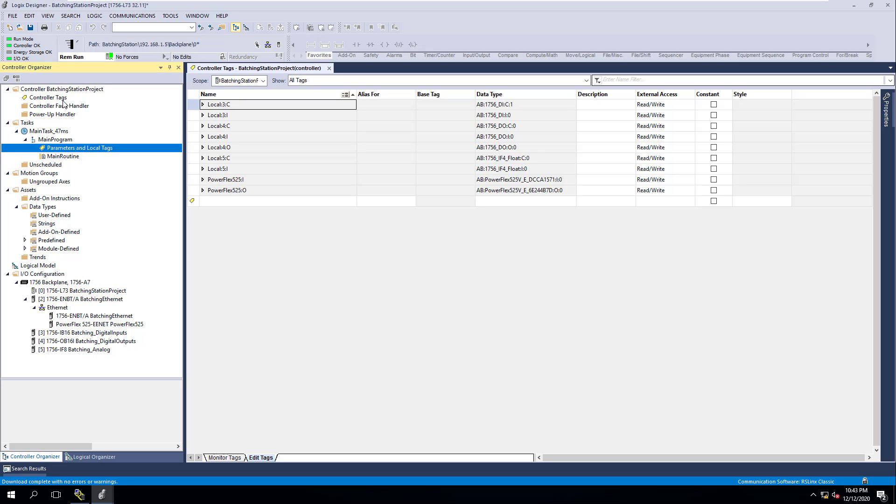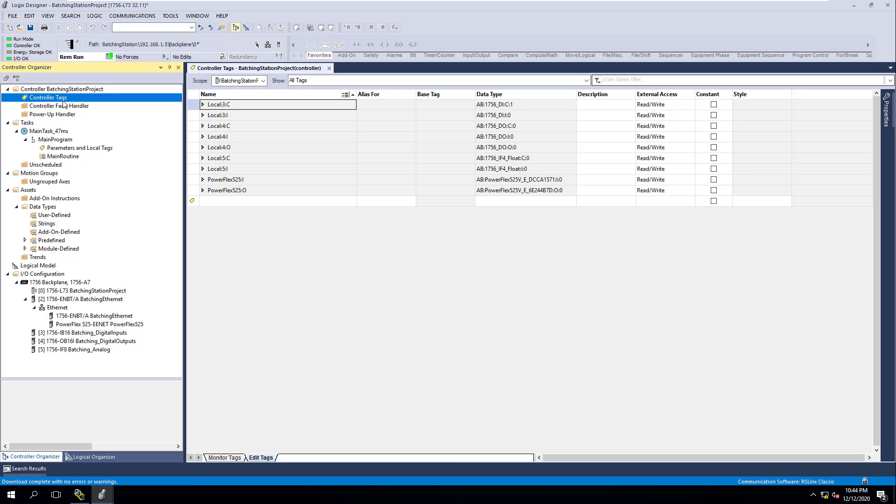These cannot be used outside of the actual task that you're using them in. But you also have your controller level. Your controller level is going to be anything that you can use anywhere inside of the program whatsoever. It's also the easiest thing to communicate to your HMIs and stuff of that nature. The controller tags are the easiest to communicate to, and everything that's in your IO tree is going to be associated with them, because these are the items that need to communicate to everything in your whole program.